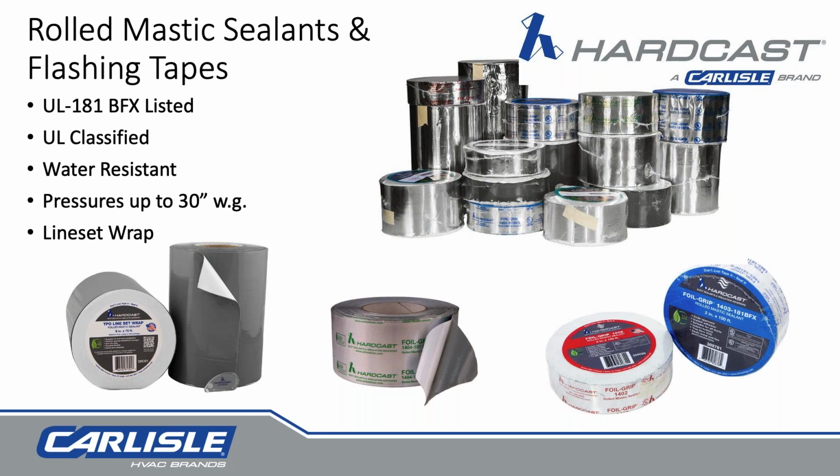Back in the early 1980s, Hardcast pioneered and still is the hands-down leader of rolled mastic sealant in that market. These are true duct sealants that will get you in and out fast without waiting for curing, and you'll have minimal labor. You can pressure test the system immediately, so there's no waiting 24 to 48 hours for the products to cure before testing. And if you think about it, that's a huge savings simply in logistics of having to come back to the job site to test. The rolled sealants can also handle pressures up to 30 inches of water gauge.